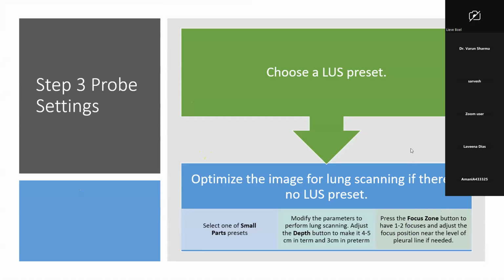The one last thing: most of your machines, when you choose a lung ultrasound preset, will turn harmonics off. At the moment, I can see that for the images you're using today, in all your machines, your harmonics are definitely turned off. Now, if you use an echo probe to do a scan and it's using a lower frequency, it will have harmonics on.